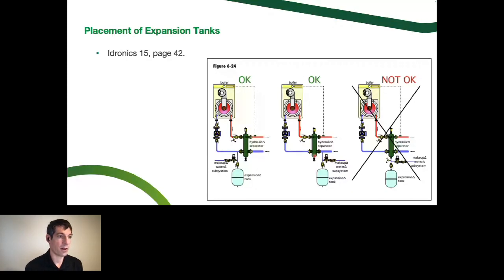An interesting part of the hydroseparators is, because the pressure drop is so minimal for the hydraulic separation to work effectively, you could actually put the expansion tank right on the right side here, and it would effectively still be pumping away, because this is such a minimal pressure drop across this vessel. If this were a balancing valve or any other sort of control valve, you wouldn't want to do that. You'd want to get that expansion tank closer, but this would be okay.